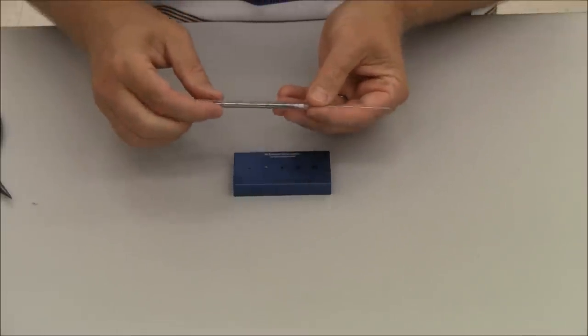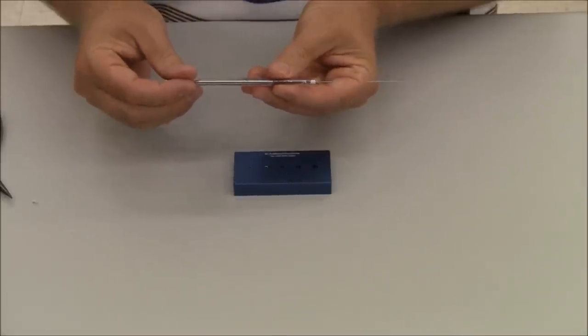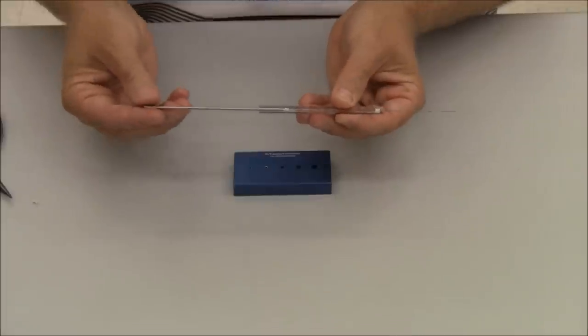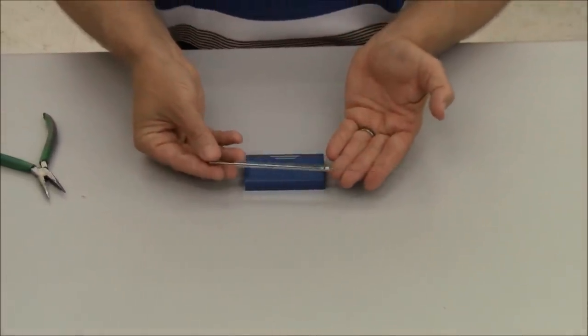Make sure when it is down, make sure the Teflon tip is all the way on the plunger. That's perfect and that is how you change the Teflon tip on a multi-syringe.